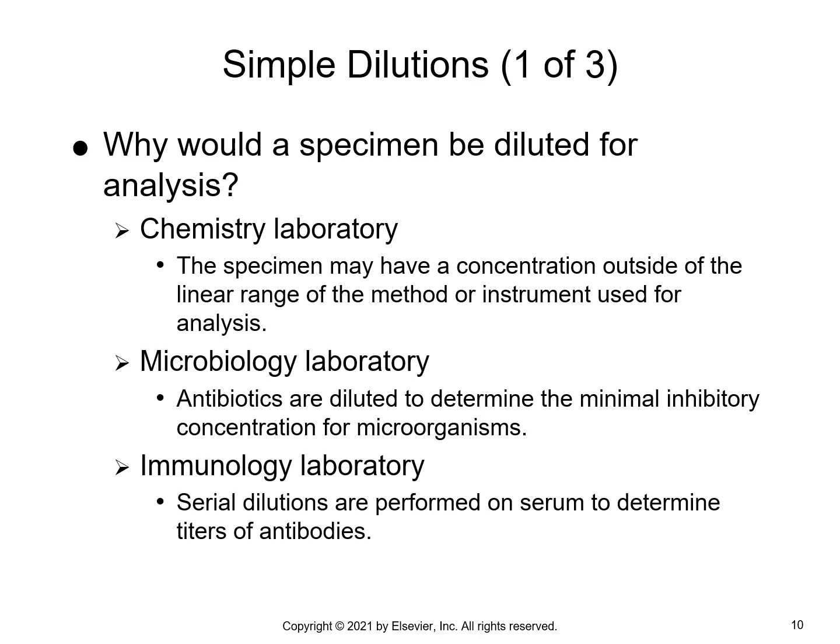Occasionally you might have something that goes above that range. An example of this would be something like a beta HCG for a pregnancy test. Once those hormones start doubling about every 2.5 days, you reach a point where that hormone level is outside of the measuring range of that instrument. That would be an example of where you would need to do a dilution on the patient sample in order to get that value within a range in which the machine can measure. And then from there, you would do calculations to figure out what that result actually is.